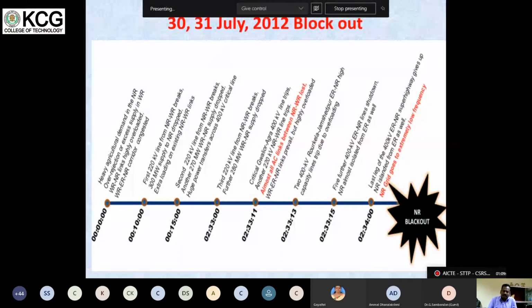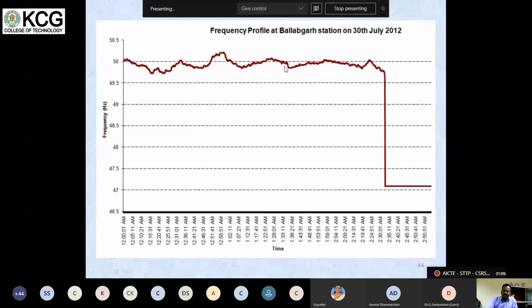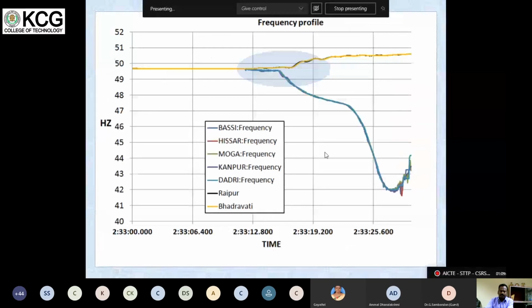That means we should be able to know what the demand, the load and the generation are. So we have to match the generation and the load in the system. That is an important work of the power players in this system. You see here, the frequency goes down at 2:33. The frequency was oscillating at nearly 50 Hz. At the time of failure, at 2 hours 34 minutes, you can see the frequency goes down very drastically. This is the reason for the total blackout. You can see here, this is the northern region grid system, and here you can see the western region side. The western region was maintained, but the northern region, since it was drawing more power, the frequency went down.